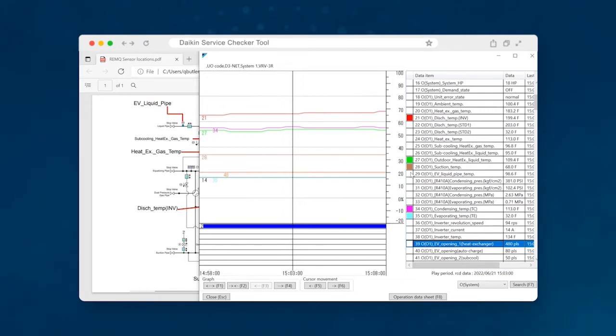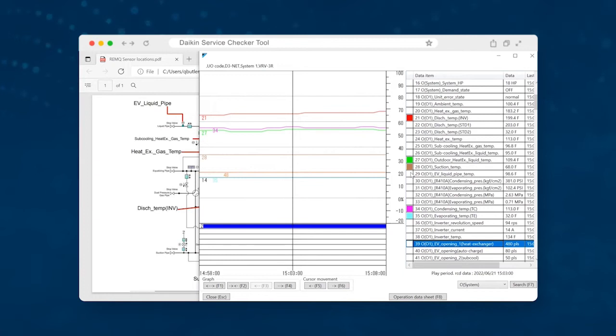So from this, we have deduced that the system is low on refrigerant charge. And so now we can talk about, okay, what do we need to do to fix this? Can we top it off? Can we leave it? In an emergency situation, you may have to top the system off to get, it may be a hotel or a school or something like that, where they need cooling. Now, you can top the system off. But you need to go ahead and have your plan in mind, discuss with your customer about how we're going to actually fix this permanently.